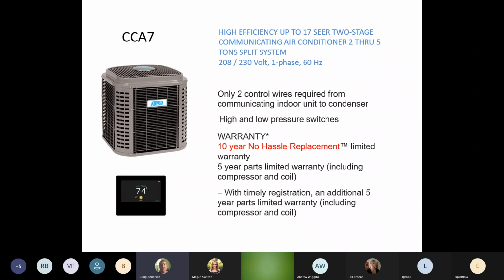So it can wire in with the ion stat, or it can be wired in with just a 2-stage thermostat with a 2-stage furnace, a 2-stage capability. If it's a communicating, we only need 2 wires to the outdoor unit. So very handy if you're doing a retrofit and you want a communicating indoor unit or outdoor unit, sorry. It only needs a 2-wire to operate.